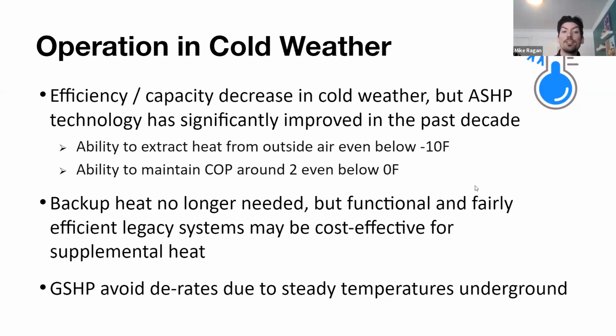In addition, ground source heat pumps, if we're talking about water source equipment, this is not air source equipment, will even further avoid any derates associated with cold ambient conditions by utilizing steady temperatures of groundwater underground. That's going to have very, very little deviation over the course of the year for that groundwater supply. So that effectively eliminates any derates associated with winter conditions.